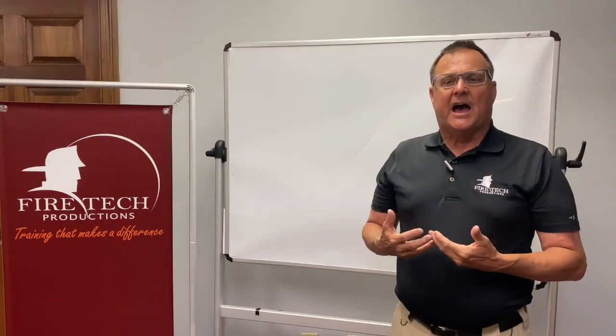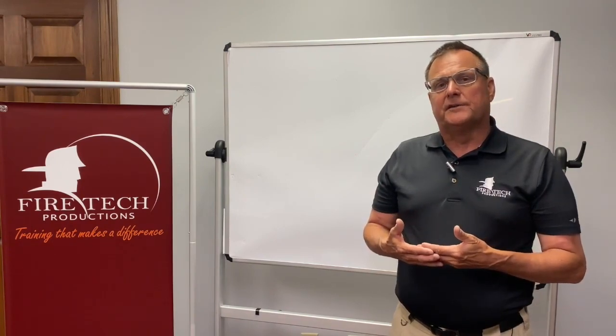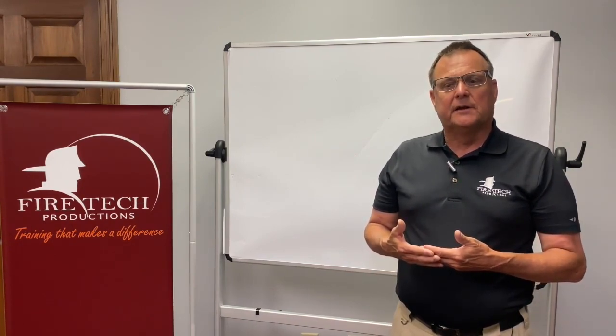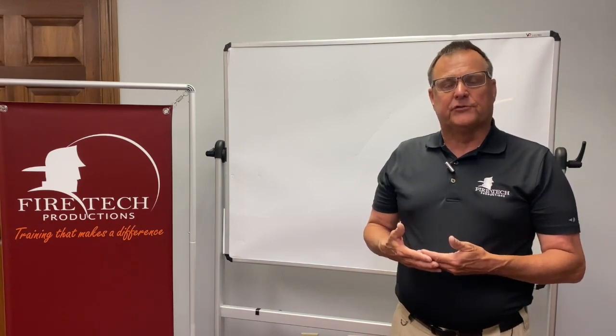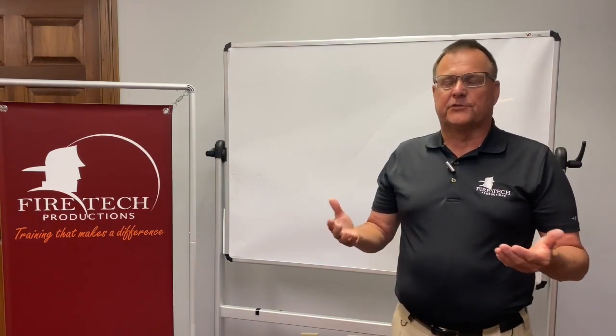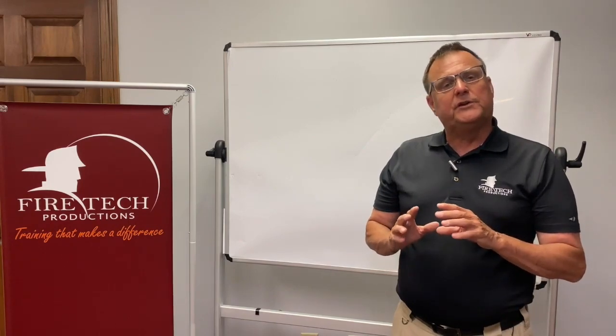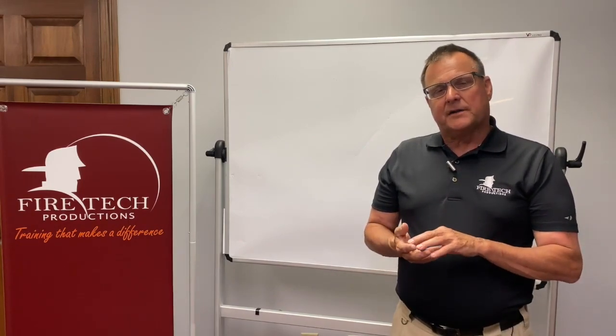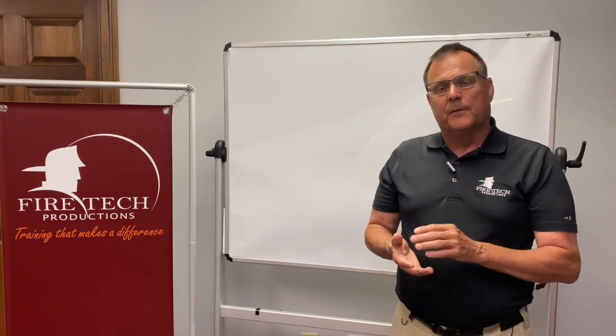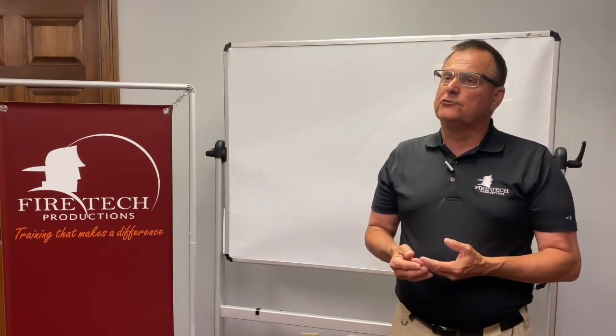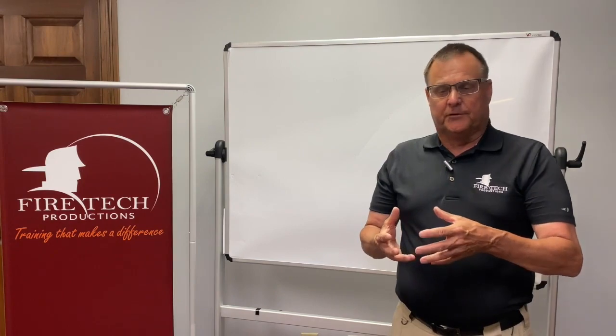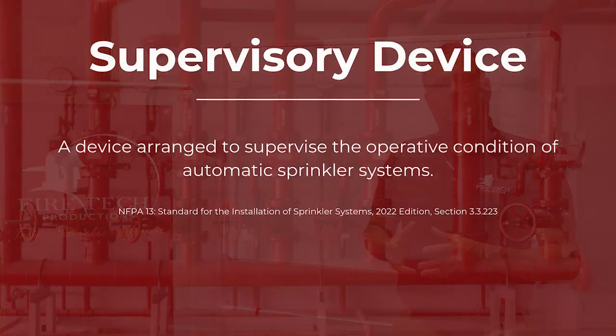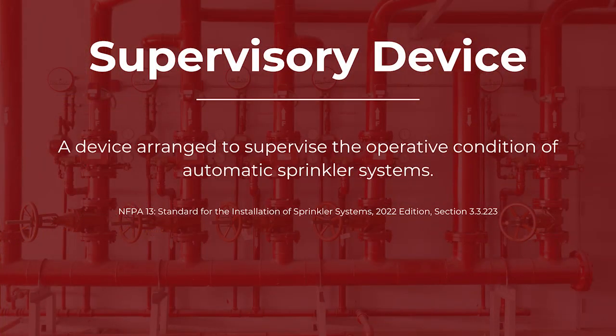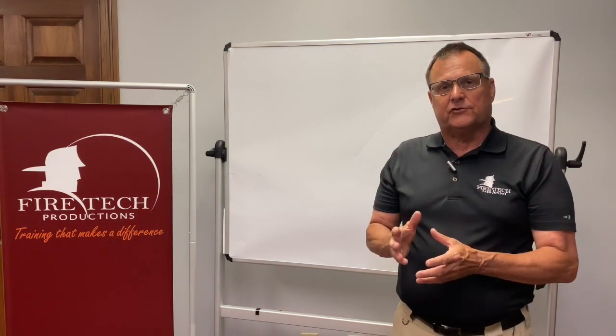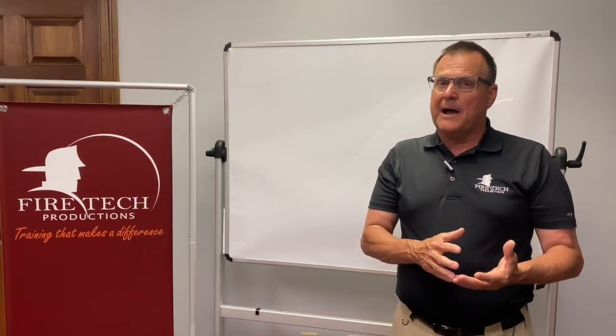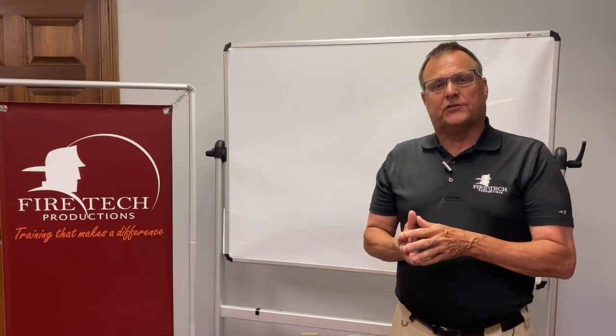Many buildings today have a combination of a fire alarm and detection system as well as a fire suppression system, for example a water-based sprinkler system. What we do is use the fire alarm panel to monitor that fire suppression system, whether it be the status of the valves controlling the water supplies through a supervisory switch affixed to that valve, so that we know if that valve for some reason is turned into an abnormal condition, meaning the sprinkler system might be impaired. We can monitor the status of the valve.